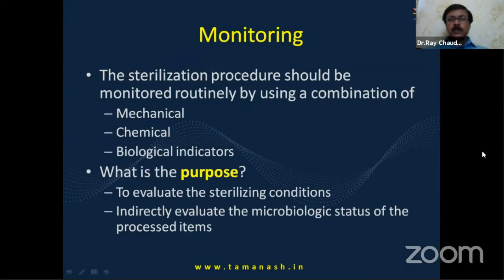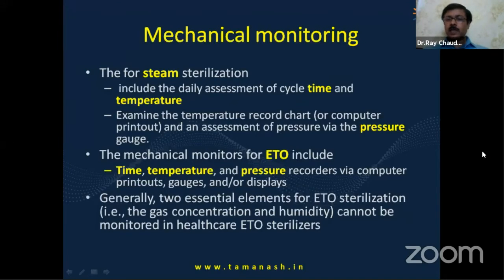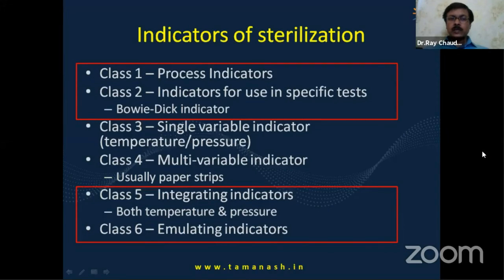Now, monitoring of sterilization will be by either mechanical means, that is pressure gauges, which I will not cover, or with chemical and biological indicators, which I will cover, which is most important. And the purpose is to evaluate the sterilizing conditions and indirectly evaluate the microbiological status of the processed item. You cannot directly evaluate the microbiological status of a sterilized instrument. So for indicators, there are class 1 to class 6 indicators, of which we commonly use class 1 and class 2 and class 5 and class 6.